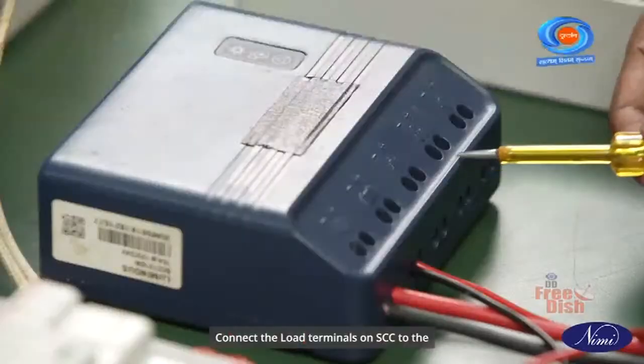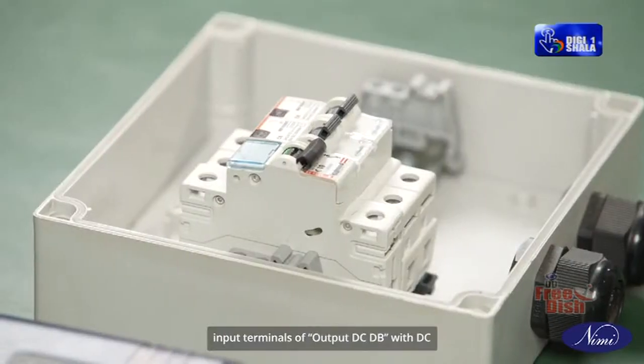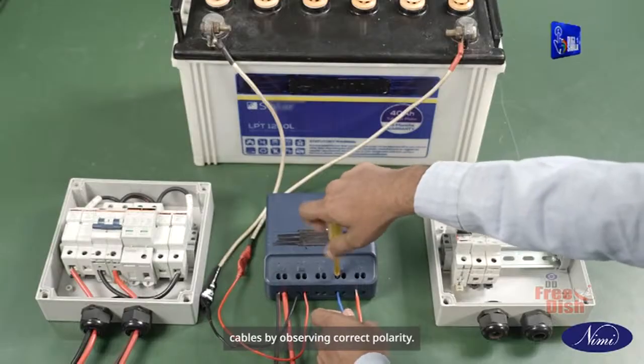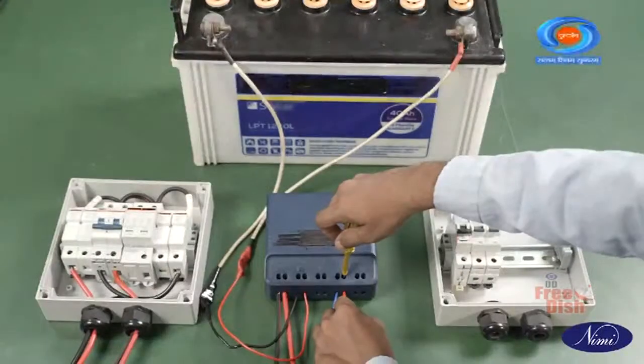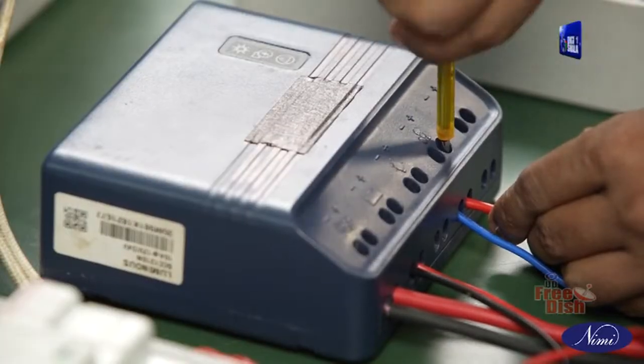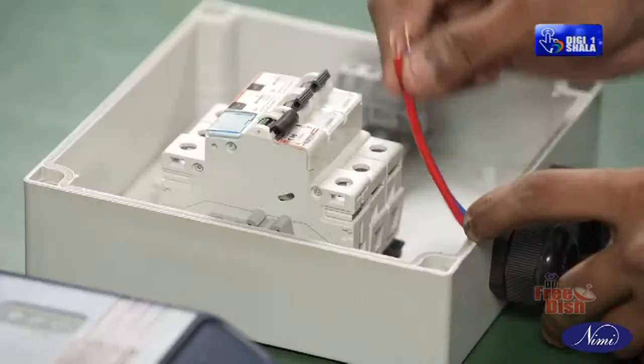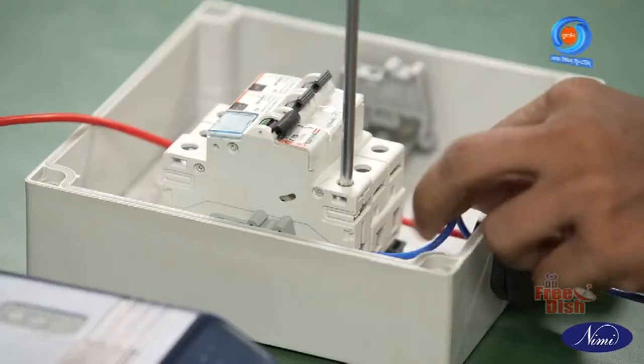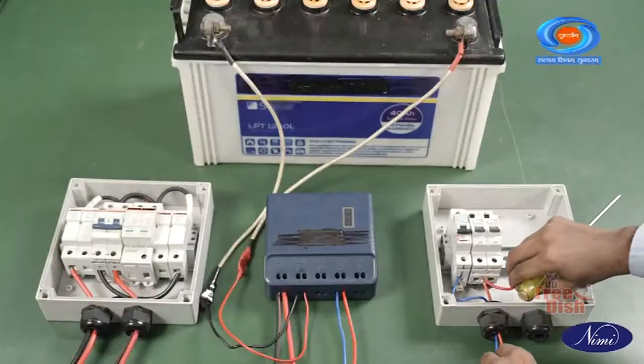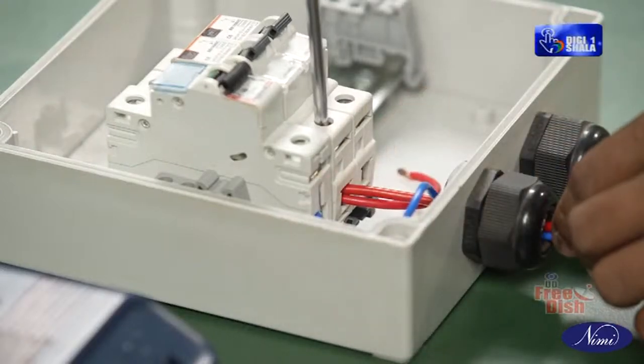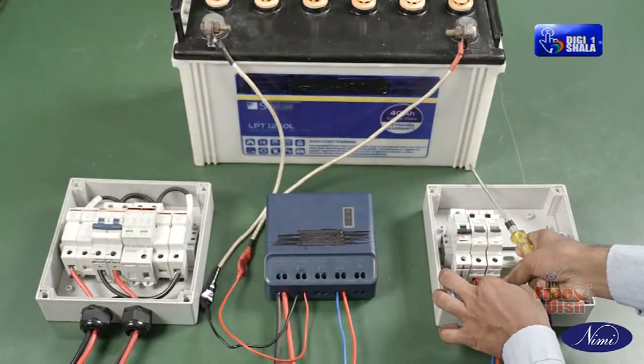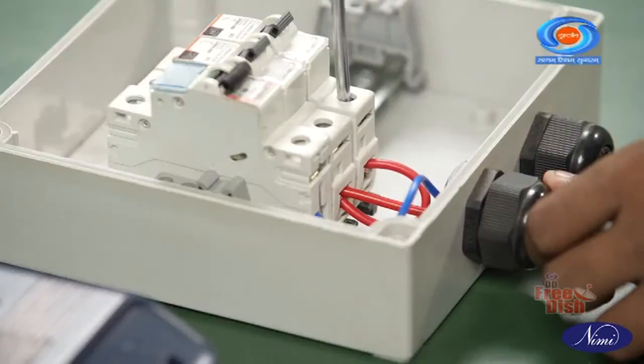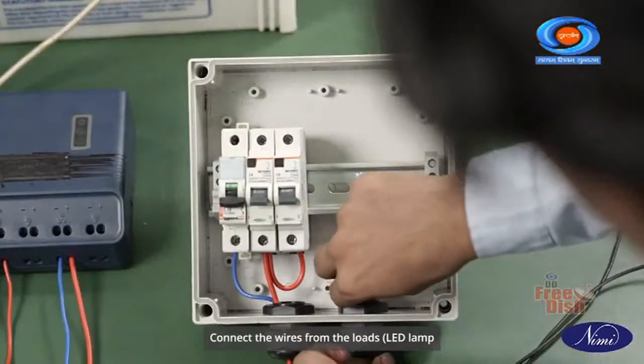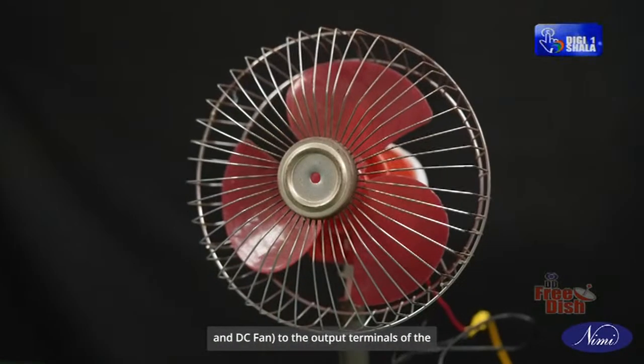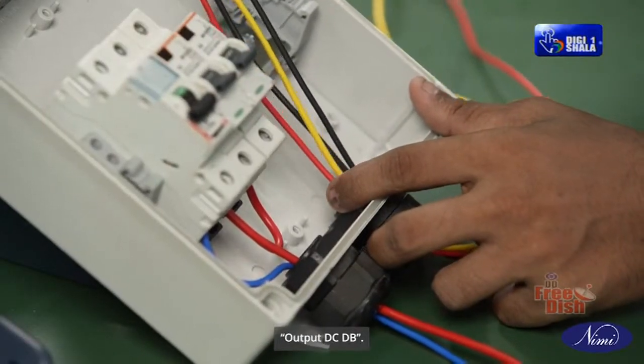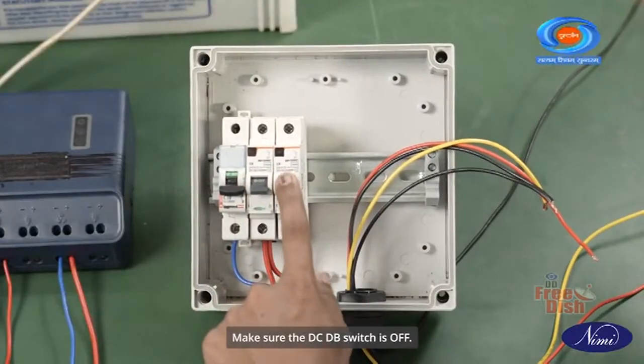Connect the load terminals on SCC to the input terminals of output DC-DB with DC cables by observing correct polarity. Connect the wires from the loads, LED lamp and DC fan to the output terminals of the output DC-DB. Make sure the DC-DB switch is off.